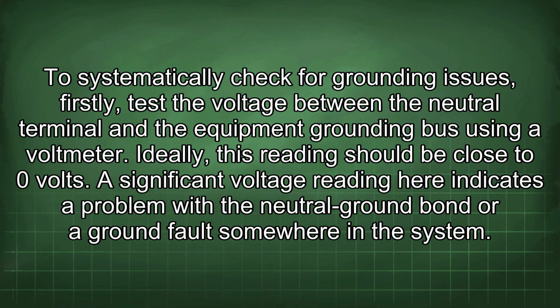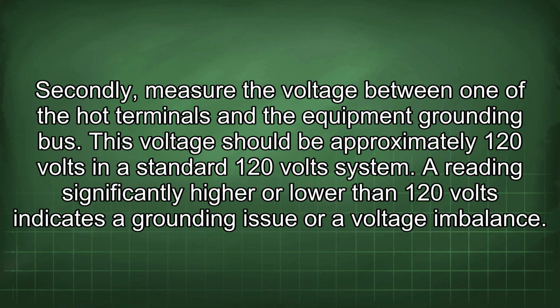To systematically check for grounding issues, firstly, test the voltage between the neutral terminal and the equipment grounding bus using a voltmeter. Ideally, this reading should be close to 0 volts. A significant voltage reading here indicates a problem with the neutral ground bond or a ground fault somewhere in the system. Secondly, measure the voltage between one of the hot terminals and the equipment grounding bus. This voltage should be approximately 120 volts in a standard 120 volts system. A reading significantly higher or lower than 120 volts indicates a grounding issue or a voltage imbalance.